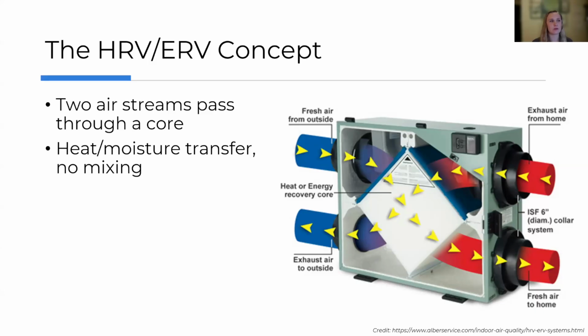So the HRV or ERV concept: you have your heat recovery ventilator and your energy recovery ventilator, controlling airflow into and out of the building. For an HRV, stale air leaves the building and passes through the heat transfer core, while fresh air from the outside is tempered so it gets a bit of a heat boost. In ERVs, moisture is also transferred to help better maintain humidity levels in the building. The result is fresh, filtered, preconditioned air at a fraction of the energy cost.